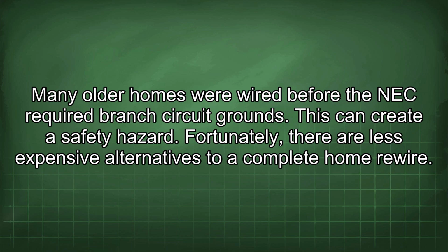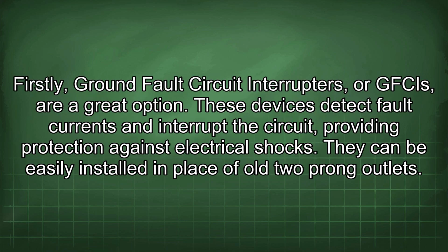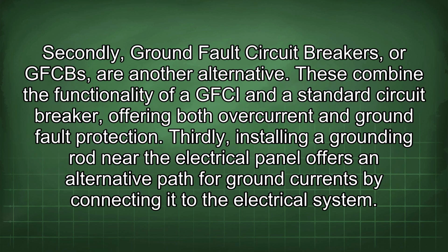Fortunately, there are less expensive alternatives to a complete home rewire. Firstly, ground fault circuit interrupters, or GFCIs, are a great option. These devices detect fault currents and interrupt the circuit, providing protection against electrical shocks. They can be easily installed in place of old two-prong outlets. Secondly, ground fault circuit breakers, or GFCBs, are another alternative. These combine the functionality of a GFCI and a standard circuit breaker, offering both overcurrent and ground fault protection.